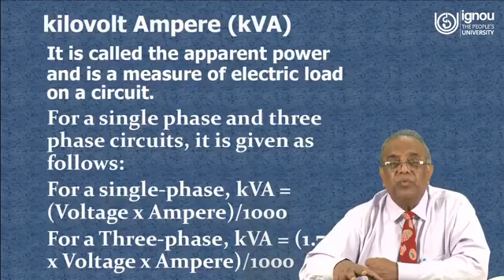For single phase and 3-phase circuits, the expressions are different. For a single phase, KVA is equal to voltage into ampere divided by 1000. For a 3-phase, KVA is equal to 1.732 into voltage into ampere divided by 1000. Why are we dividing by 1000? Because V into A, voltage into current, gives power in watt. We are dividing by 1000 to convert it into kilo. For a 3-phase, the expression is √3 voltage into ampere by 1000. The value of √3 is equal to 1.732.